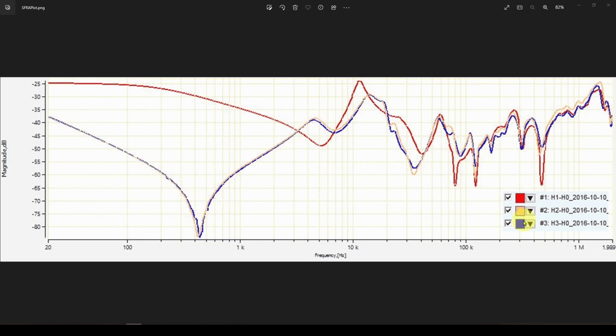You can see we've got 3 windings, red, green, and blue, on top of each other, and even with different windings there's quite a bit of variation. You can imagine this would be supplied by the manufacturer upon building the new known-good transformer, and then in later years the utility or industrial customer can perform a similar test to see if any of this changes, which might be a good indication of a problem with the transformer.